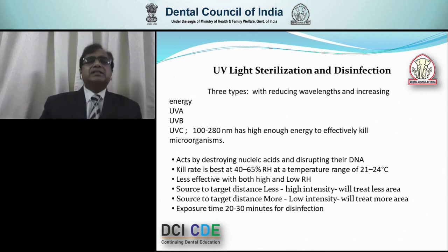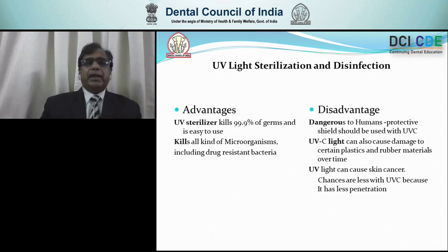As I have said, UV light sterilizers kill 99.9% of germs, are easy to use, and kill all kinds of microorganisms including drug-resistant bacteria. The disadvantages are that they are dangerous to humans, so protective shielding should be used with UV-C lights. UV-C light can also damage certain plastics and rubber materials over time, and UV light can cause skin cancer, but the chances of skin cancer with UV-C light are very low because of its low penetration.